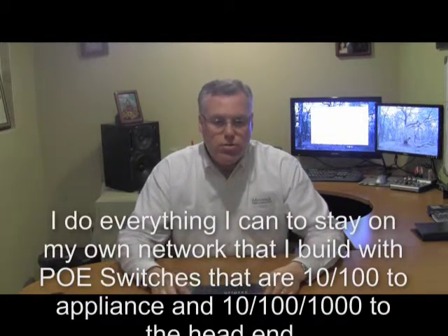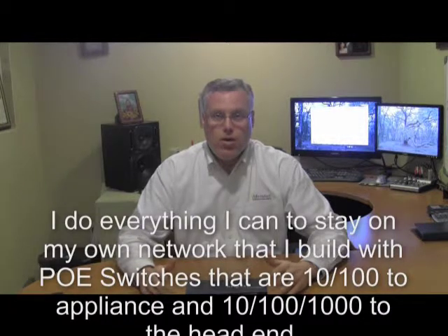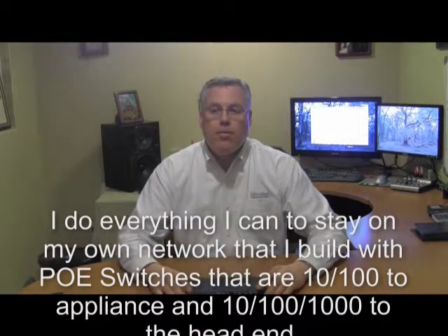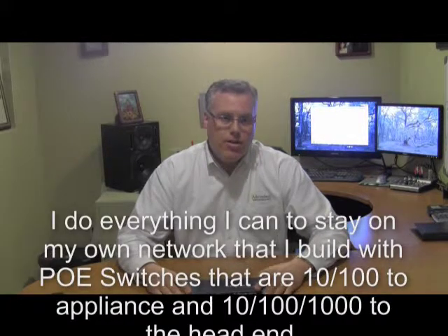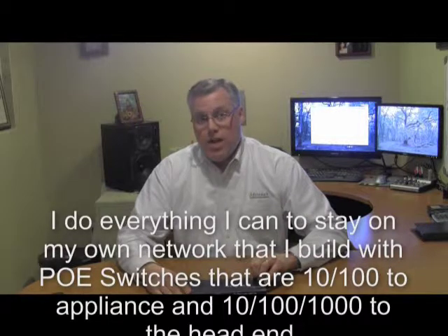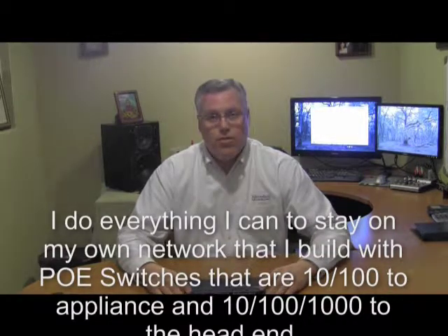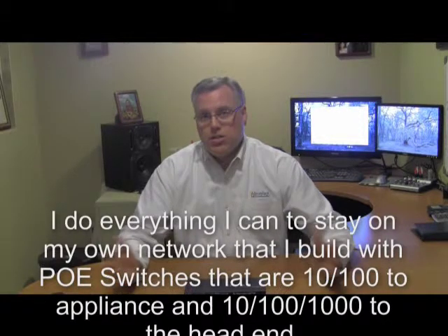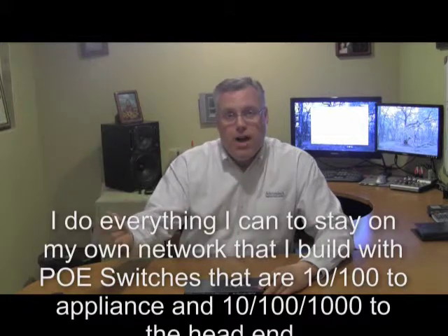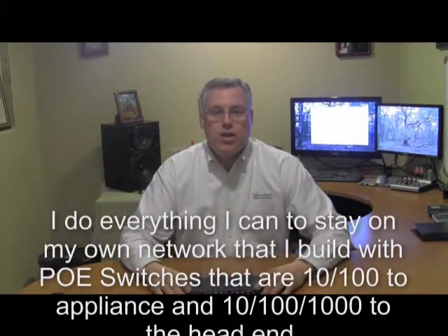Now, if you walk into like a school or a university or a hospital and they have an existing network, they're probably going to have network appliance criteria, and they're probably going to want you to put products on their network. I don't like that, but in some cases we have to. Now, in those cases, many times they don't have a power over Ethernet switch. They'll have a big Cisco switch, but it doesn't supply power. Or let's say it supplies class 2 power, and we know that we want to stay on class 3. At that point in time, we'll put a midspan in.